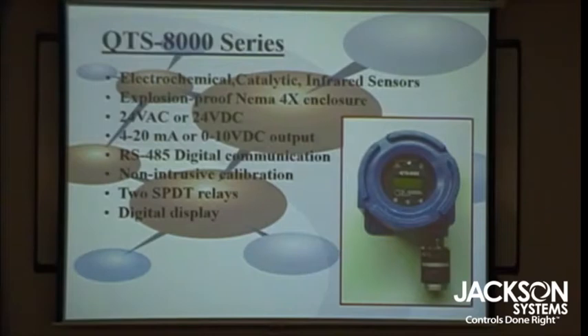And that's what it looks like. This is the QTS 8000 series. This was the one that we designed for NASA, but we will use it in industrial applications. It comes with relays, Modbus, RS-485 communication, and 4-to-20s. And the reason we say non-intrusive calibration is that you don't have to open it up to calibrate it. In classified areas where you have, let's say you're in a plant where there's a lot of these nasty gases around, if you open it up and you accidentally cause a spark, you can cause an explosion.